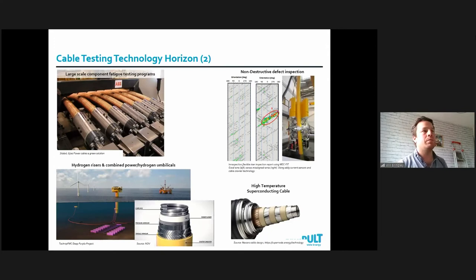And in general, the look ahead is we'd like to see a large scale test program so we can learn as much as possible about these cables before there's thousands of them out there. But also the problem about how do you know a component's failed in your cable without cutting it? Well, there's some technology from oil and gas that we'd like to test to see if you can detect things like armor wire failure through eddy current. That's what's on the top right there. For a riser, you can detect that corrosion and fatigue, so you should be able to do it for a power cable.